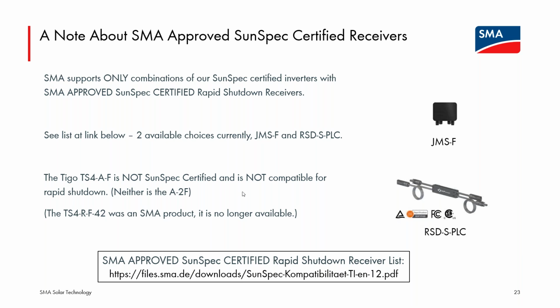I want to emphasize this because there's been a lot of customer confusion. The Tigo TS4-A-F or the A-2-A-2F, neither of those devices is certified by SunSpec. Only devices that are on the SunSpec certified list are going to go through SMA approval testing. So neither of these two devices is on the approved list. SMA supports only combinations of devices off of the approved list with our inverters with the SunSpec certified transmitters, so the CORE1 US-41 and the Sunny Boy US-41.